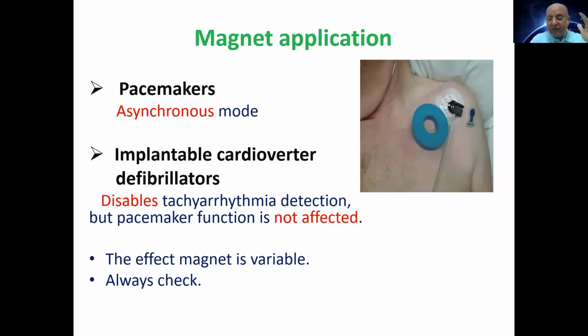As we said, the magnet effect is variable, and always check preoperatively what the type is, because this magnet effect depends on the type of the pacemaker. Not every pacemaker has, as I said, a magnet sensor. Not every pacemaker responds in the same way.